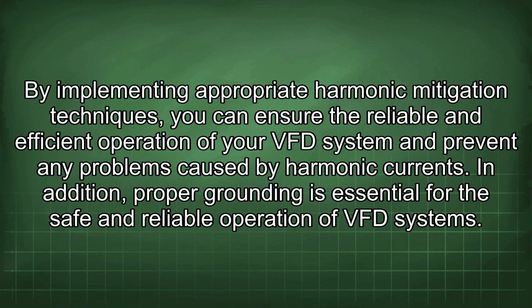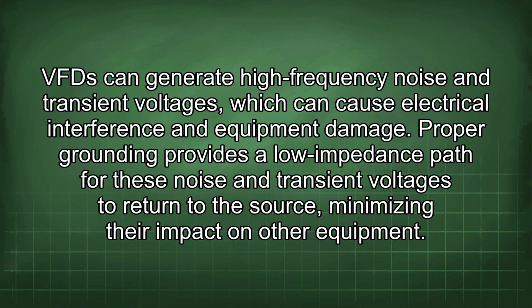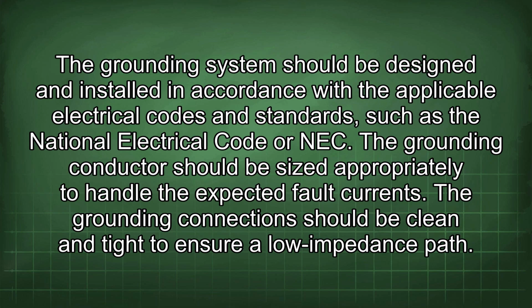In addition, proper grounding is essential for the safe and reliable operation of VFD systems. VFD can generate high-frequency noise and transient voltages, which can cause electrical interference and equipment damage. Proper grounding provides a low impedance path for these noise and transient voltages to return to the source, minimizing their impact on other equipment. The grounding system should be designed and installed in accordance with the applicable electrical codes and standards, such as the National Electrical Code or NEC.